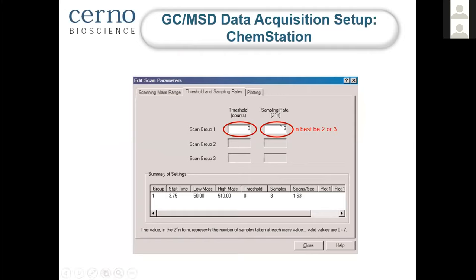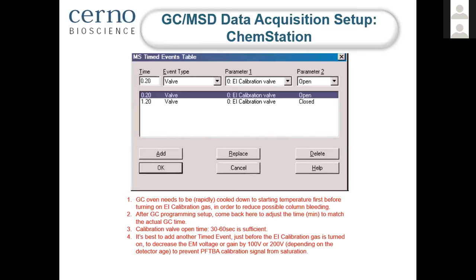in order to get the true profile data. And then the sampling rate in Agilent terminology is represented by the number of points averaged. Typically we recommend setting it to 2 or 3, which corresponds to medium scanning speed in terms of how many seconds it takes to scan 1,000 AMU. It's right in the middle of the range. And then we need to program the calibration gas, whether you are doing the EI mode or the CI mode. The calibration gas can be turned on by just changing the mass spec acquisition parameters. You can program a time event to turn the calibration valve on and off, and that's sufficient to produce the calibration data we need.